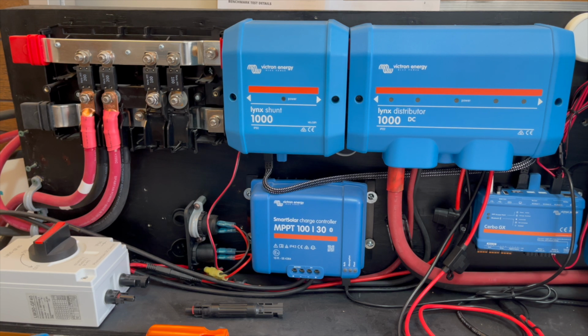It needs to come with a breaker for DC loads. You have to be sure. And a separate power switch. When connecting to your system or inverter, or if you have another bus bar outside the server rack, you do not want to use the same gauge that each server rack uses to connect to the bus bar. From what I see, most of the units are using a number 4, number 3 in that range to the bus bar, which is adequate.